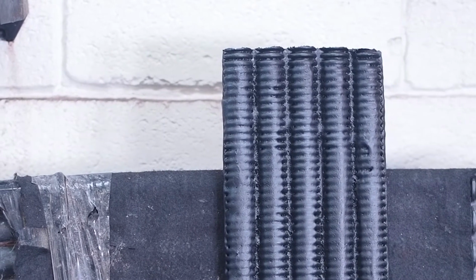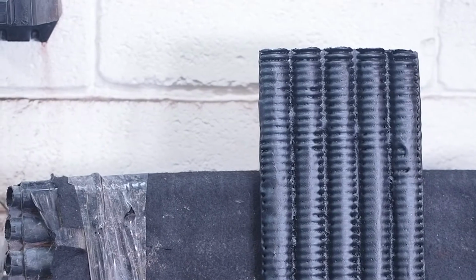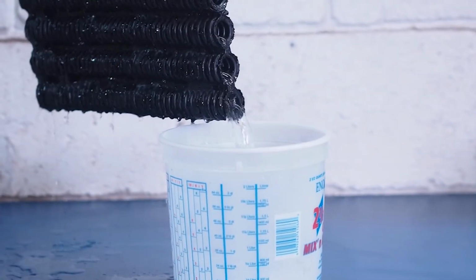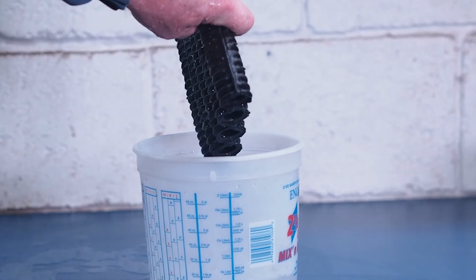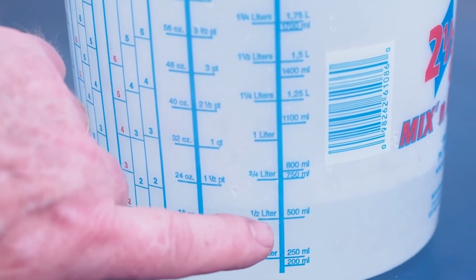This product is also intended to be installed level in order to have access to the cleanouts. Flow rate is affected by the corrugations and lack of downhill slope. Unpressurized, we assume the flow rate in reality is significantly lower than the published rate. We sealed the MultiFlow drainage conduit in order to check holding capacity, which is 1/2 liter.